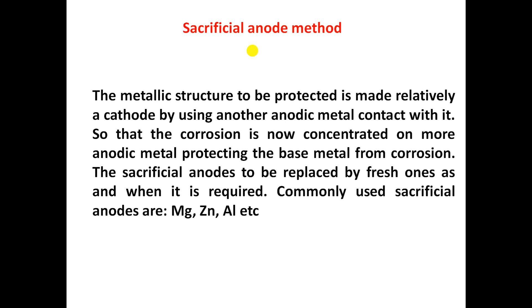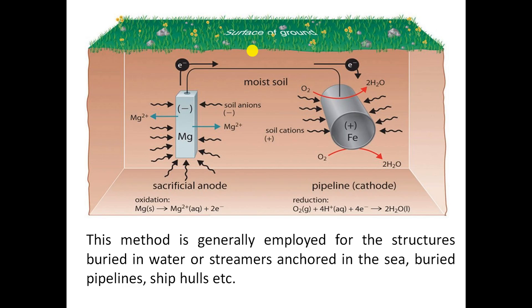The sacrificial anode is replaced by fresh ones as it is consumed continuously whenever required. Commonly used sacrificial anodes are magnesium, zinc, and aluminum. The more active metal is connected to the base metal through an insulated copper wire. Consider an iron pipe present inside moisture-containing soil. If moisture is present, the iron will generally undergo corrosion. In order to prevent this, we use a metal more active than iron — in this case, a magnesium metal bar connected to the iron pipe through an insulated copper wire.